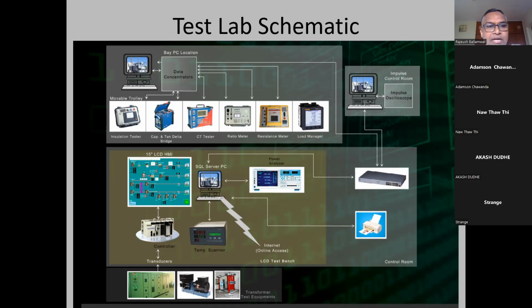therein you see the computer screen. Then you have the data concentrator, which communicates with the low voltage test instruments. To name them, it could be an insulation tester, a capacitance and tan delta bridge, a CT tester, a ratio meter, a resistance meter - that's winding resistance meter, turns ratio meter - or simply a load manager for magnetic balance tests.